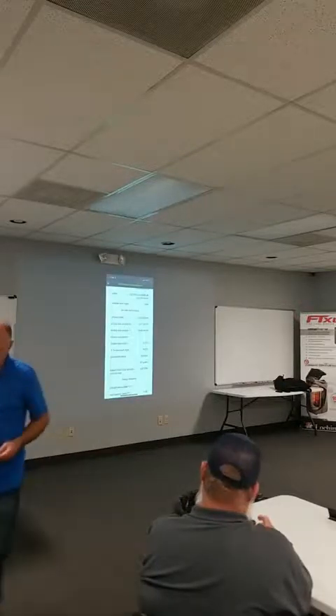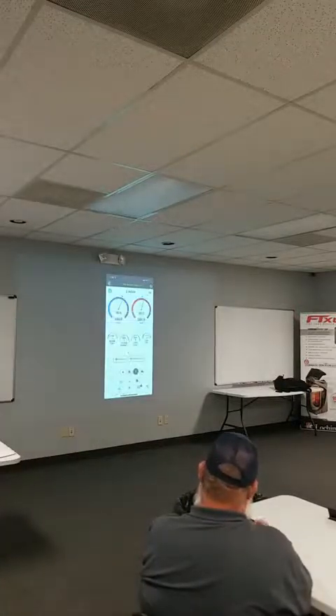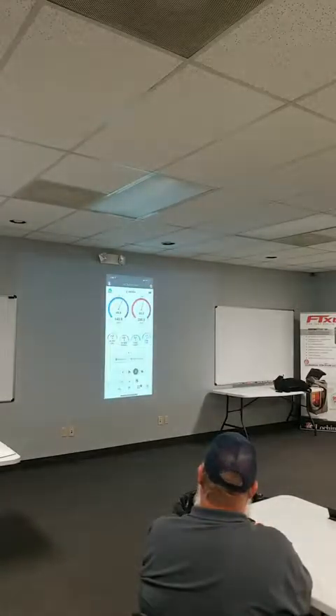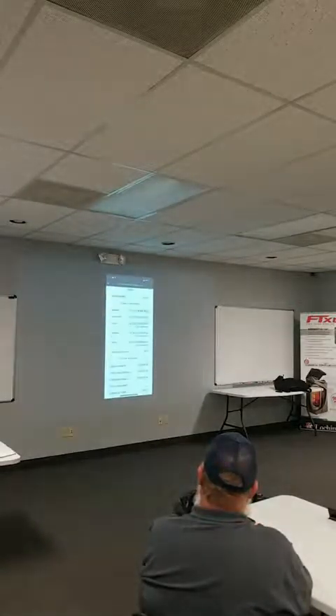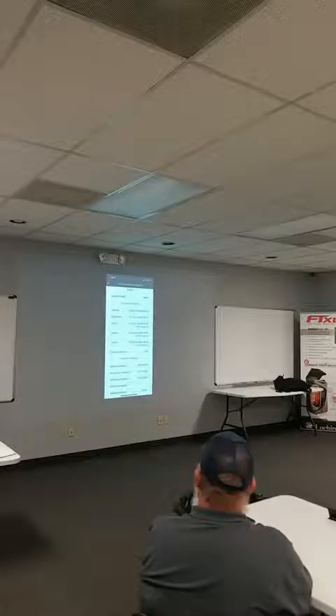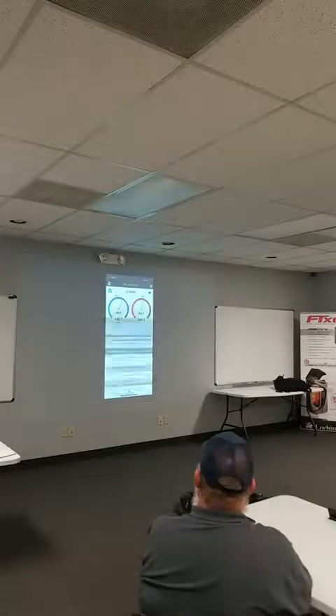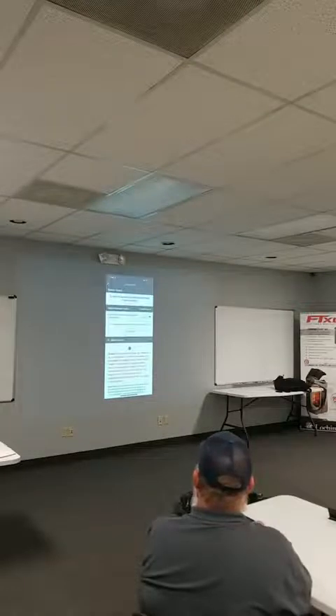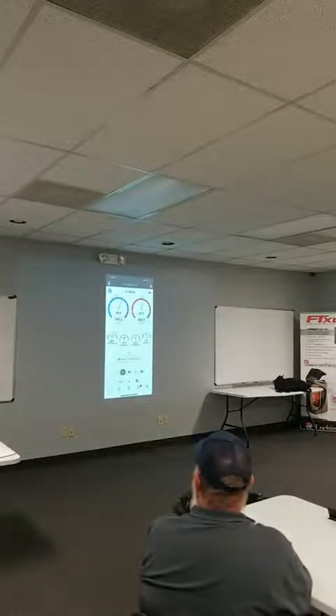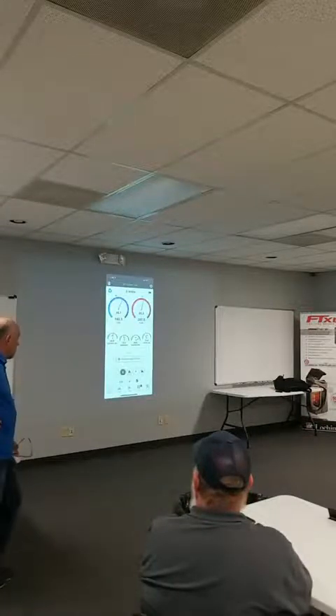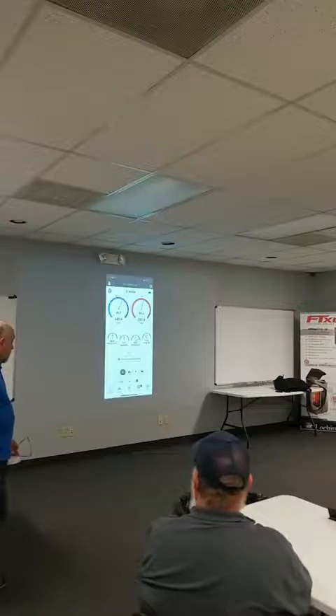Let me ask you a question, Jim. When we started, originally, the subcooling let us down. We overcharged that. So when we pulled it out and weighed it back in and came up with the same problem, is it really a problem at this point? Subcooling? Well, the manufacturer is telling us it's 3.3 or 3.4 pounds, whatever it is, and that's what we have in the equipment.